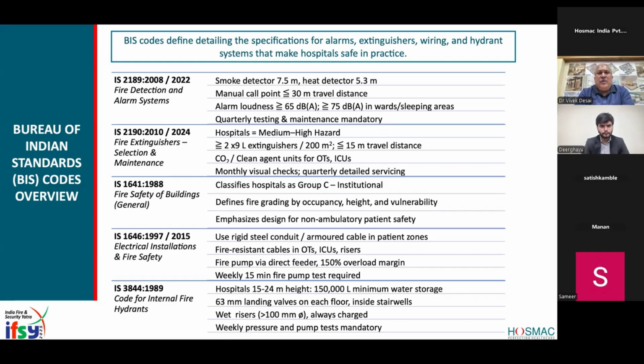that people hear it properly. And the most important is quarterly testing and maintenance mandatory. This is something that we probably miss. Then there is fire extinguishers, depending on the area, again, the travel distances and all of that. CO2 clean agent units for OT, ICUs, all of that. Monthly visual checks, quarterly detailed servicing.